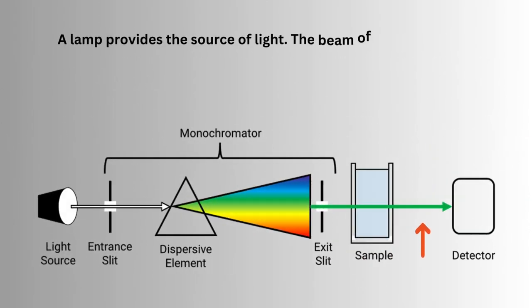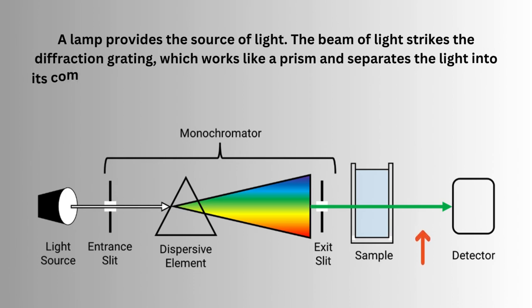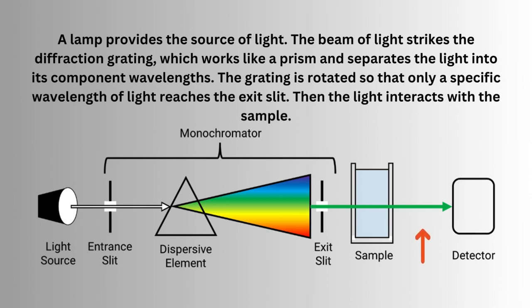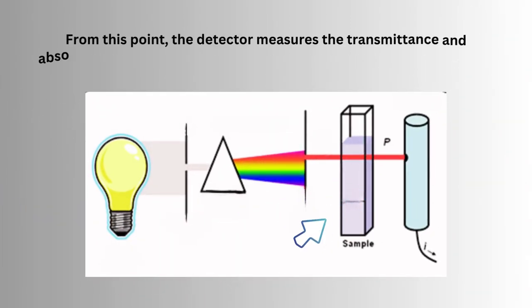The beam of light strikes the diffraction grating, which works like a prism and separates the light into its component wavelengths. The grating is rotated so that only a specific wavelength of light reaches the exit slit. Then the light interacts with the sample. From this point, the detector measures the transmittance and absorbance of the sample.